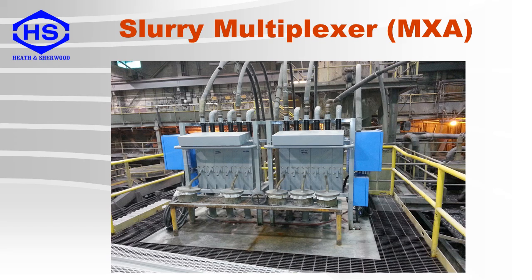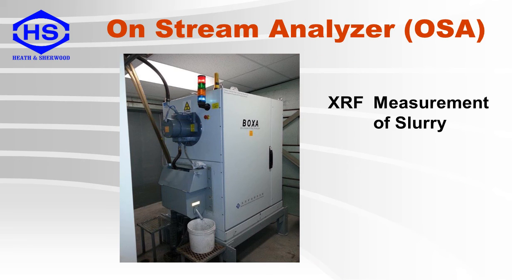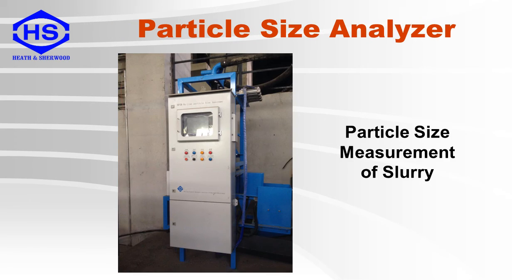Here you can see two multiplexers — in this case there are a total of six process lines connected, with a few spares also available for use. This is an example of an on-stream analyzer system where the flow cell is where the measurement takes place, using the X-ray fluorescence principle. The sample flow from a sampling system can also be directed to other types of analyzers, such as a particle size instrument.